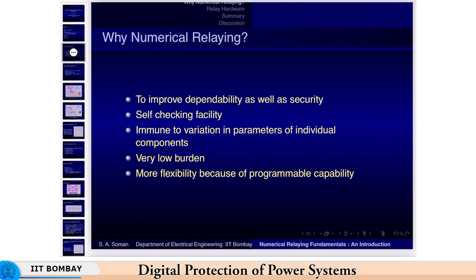The first is to improve dependability as well as security. We have seen these in detail - these two parameters define the overall reliability of the relay. Dependability is tripping when required to trip. Security is the complement, where it should not trip when not required to trip. So with numerical relaying, better processing, and more awareness of non-local data, that is global data...